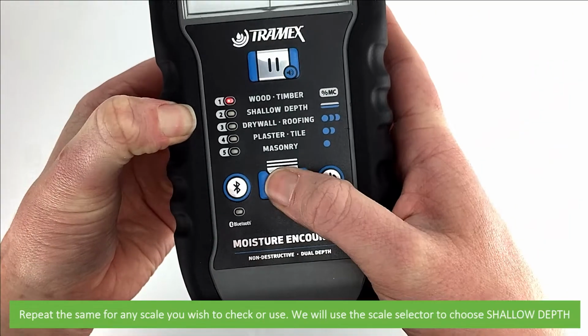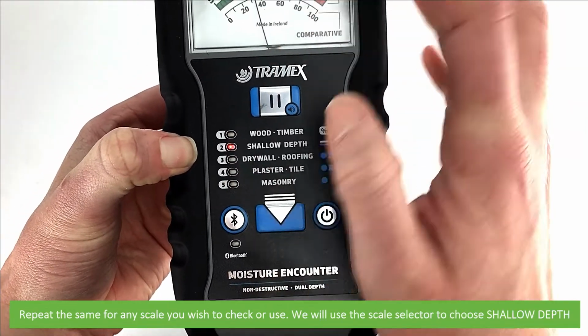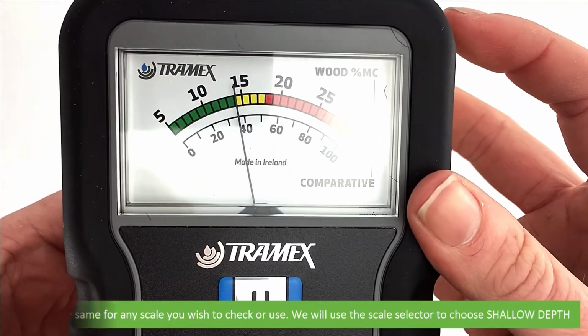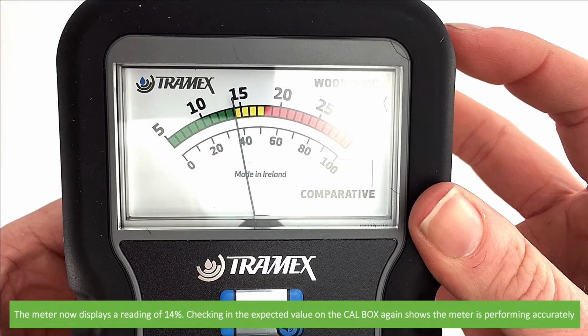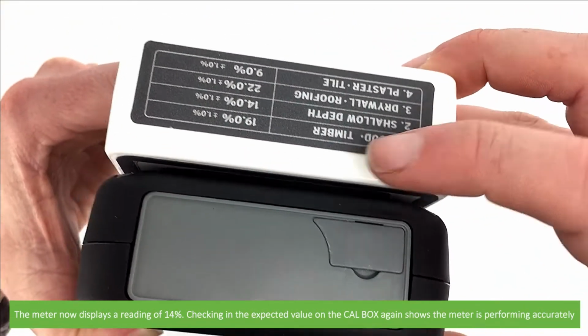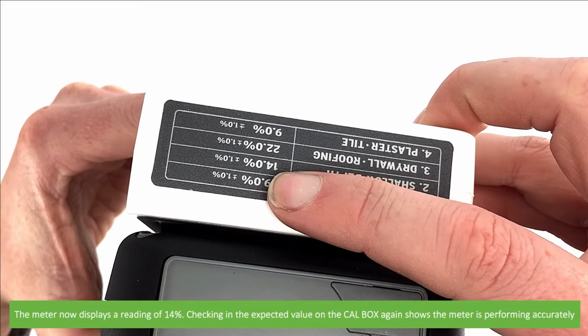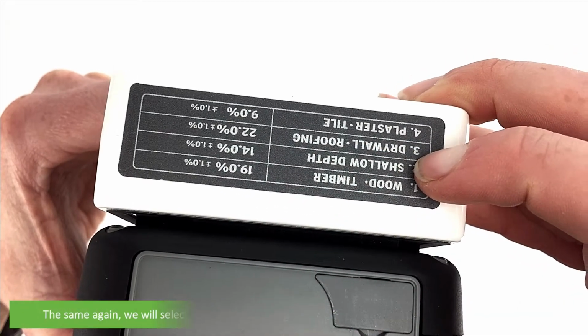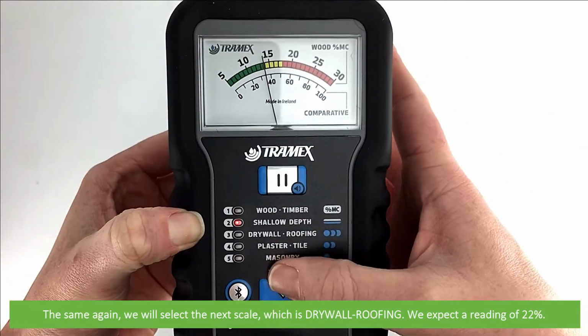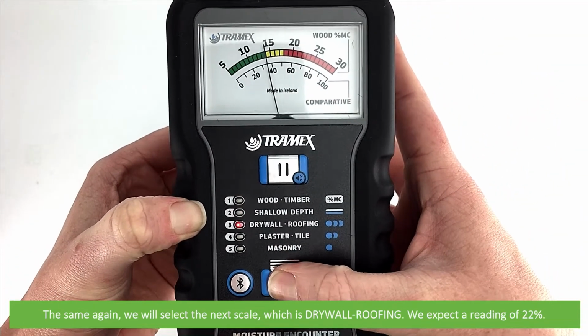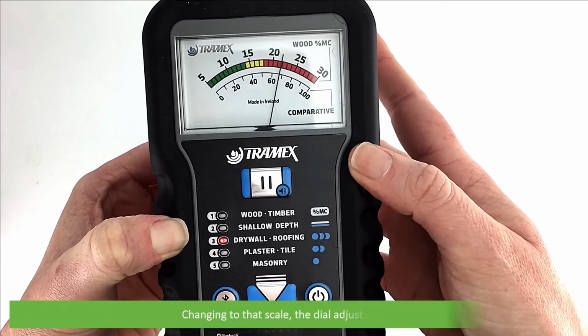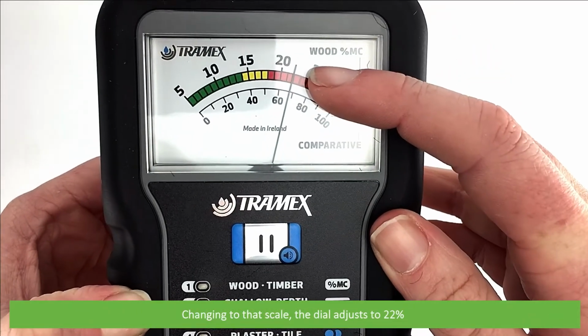Repeat the same for any scale you wish to check or use. We will use the scale selector to choose shallow depth. The meter now displays a reading of 14%. Checking the expected value on the CALBOX again shows the meter is performing accurately. The same again, we will select the next scale, which is drywall roofing. We expect a reading of 22%. Changing to that scale, the dial adjusts to 22%, right where it's supposed to be.